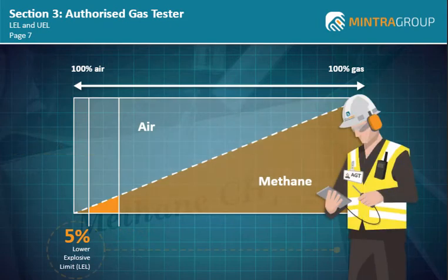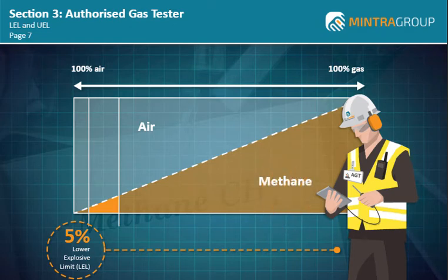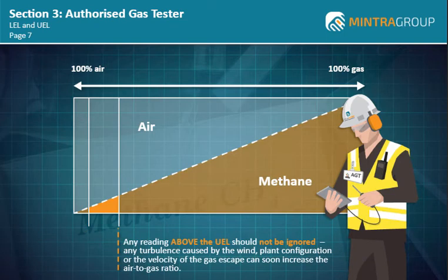As the AGT, it is the LEL which is important to you, as the gas testing equipment will alert you before the LEL is reached and will warn of the build-up of gas. However, any reading above the UEL should not be ignored. Any turbulence caused by the wind, plant configuration, or the velocity of the gas escape can soon increase the air-to-gas ratio and dilute the gas and air mix until it moves back to within the explosive envelope.